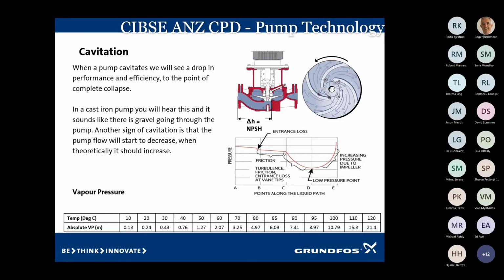That whole area is expanding 1,600 times and then contracting back down again. So you can now understand why the impellers take such a hiding. When there's all this cavitation happening within that impeller around those vanes, it's stressing the whole pump. The impeller's getting a hiding, motor bearings are getting a hiding, and eventually it will destroy itself.